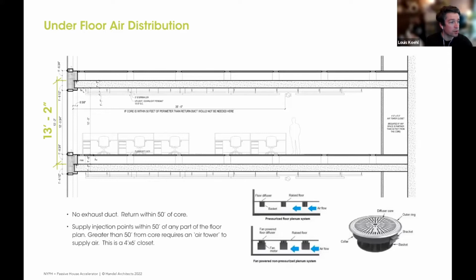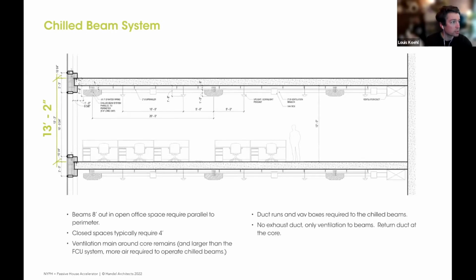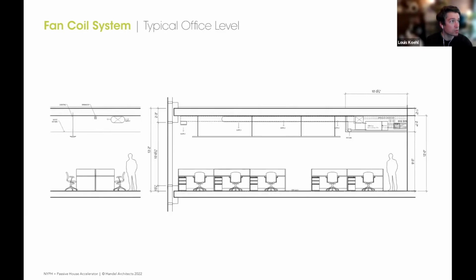Here's some sections of the different options. Underfloor air distribution, you can see this would have been an interesting option. It would have raised the floor, so it would have given a greater sensation of floor to ceiling glass. And air distribution at the floor is a very efficient way to do that. Chilled beams would have had a very strong visual impact on the project. These things are large and hard to miss when you're looking at the space. And ultimately, we went with a fan coil system where the unit can be ceiling mounted closer to the core and then ducted out to the perimeter.